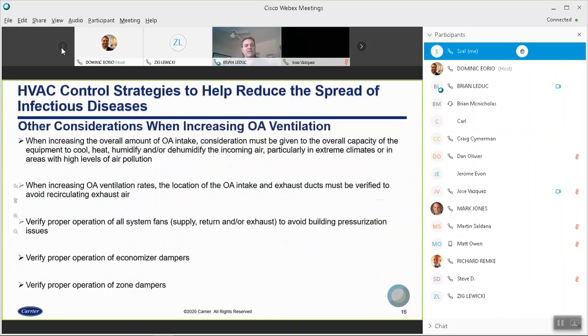Other considerations, again, I'm going to probably repeat this more than once in this presentation. The amount of OA intake that you can tolerate is going to be a function of the capacity of the equipment to cool, heat, humidify, and or dehumidify. In extreme climates, maybe even places with high air pollution, you're going to have to use caution. There's going to be limits to how much outside air you can bring in.